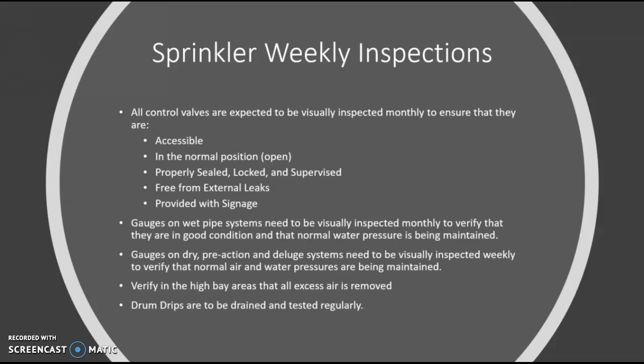Gauges on wet pipe systems need to be visually inspected monthly. They need to be verified that they are in good condition and that they have normal water pressure that is being maintained. Gauges that are on the dry pre-action and deluge systems need to be visually inspected weekly. They need to make sure that everything's maintained and available in case of emergencies.